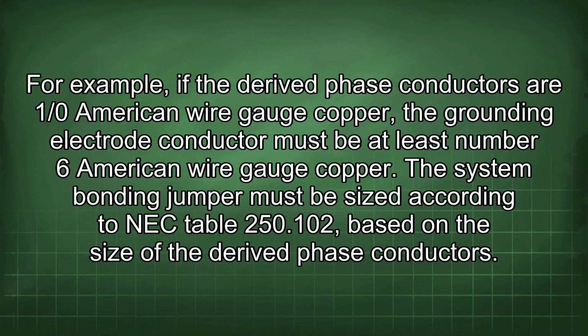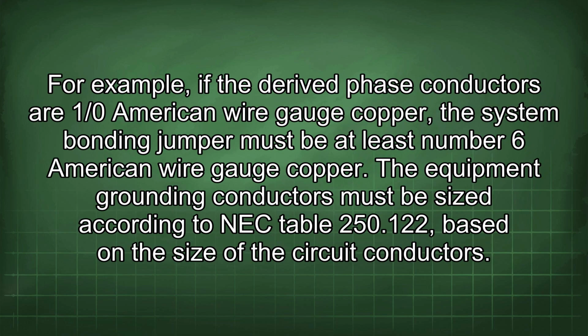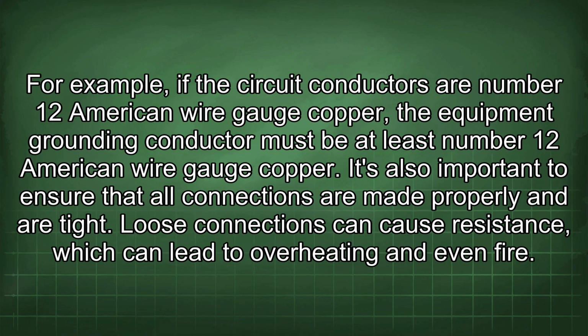The system bonding jumper must be sized according to NEC Table 250.102, based on the size of the derived phase conductors. For example, if the derived phase conductors are 1/0 American wire gauge copper, the system bonding jumper must be at least number 6 American wire gauge copper. The equipment grounding conductors must be sized according to NEC Table 250.122, based on the size of the circuit conductors. For example, if the circuit conductors are number 12 American wire gauge copper, the equipment grounding conductor must be at least number 12 American wire gauge copper.